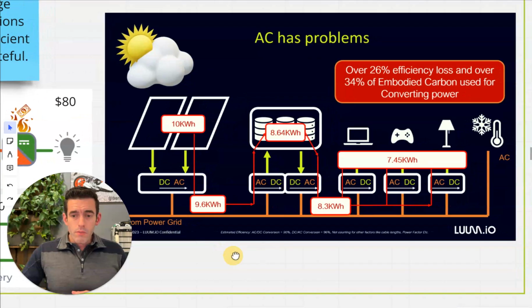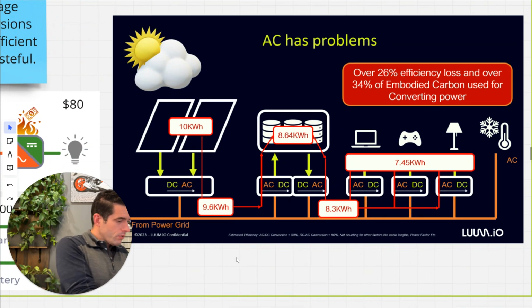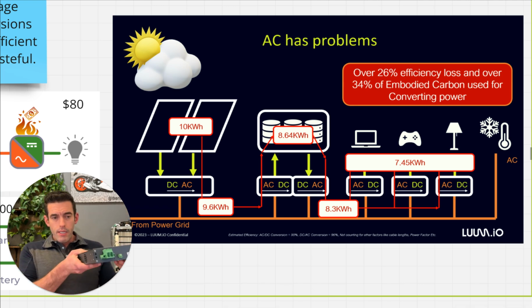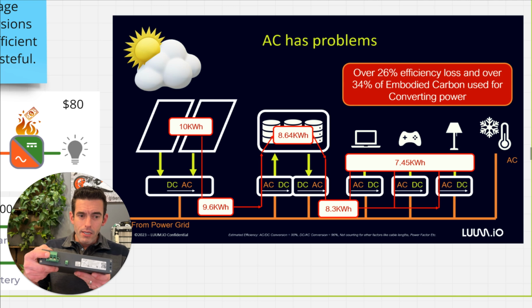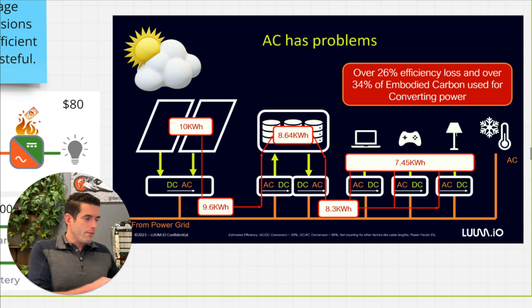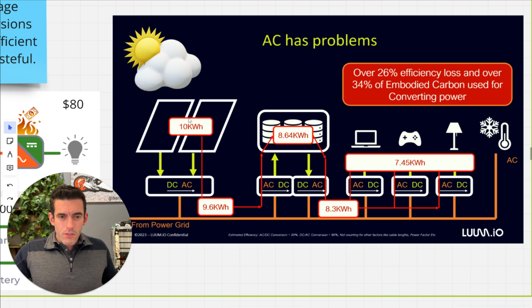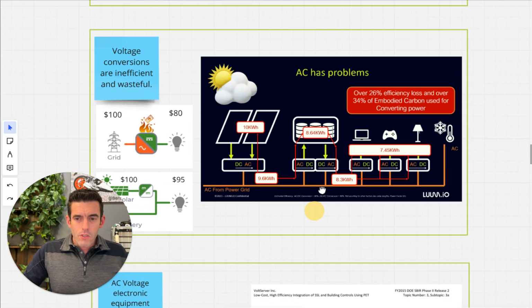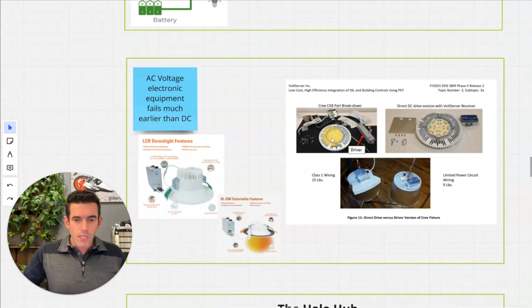One of our partnerships is with a company called LUUM.IO. I have one of their switches right here. This switch allows them to take DC power in, 48 volt DC, and on the outside we can then power all of our lights directly with this - this is a lighting driver. So instead of having all these conversion losses, going from DC to AC to AC to DC to DC to AC back and forth, every time that changes you lose about 5%. We want to reduce those conversion losses.